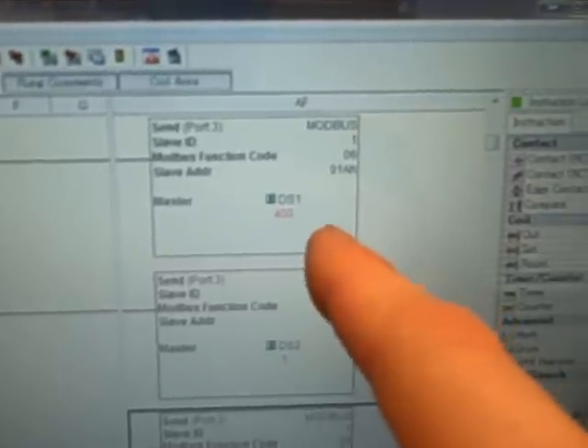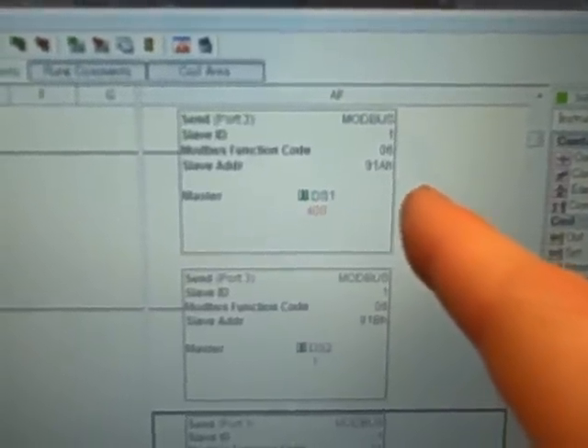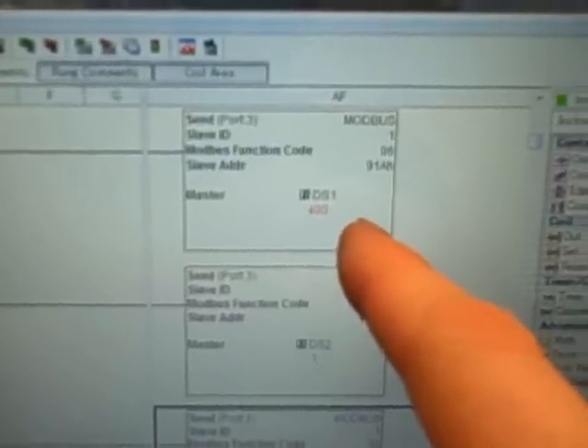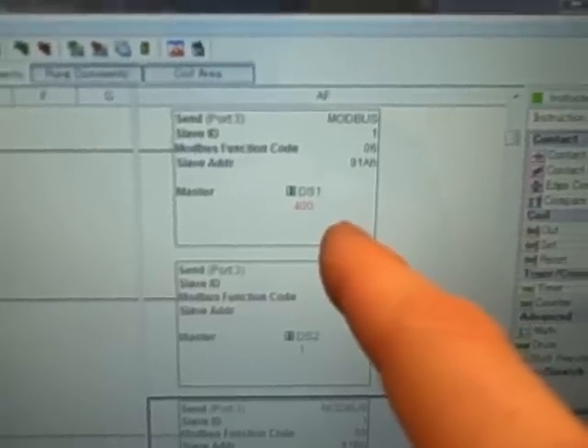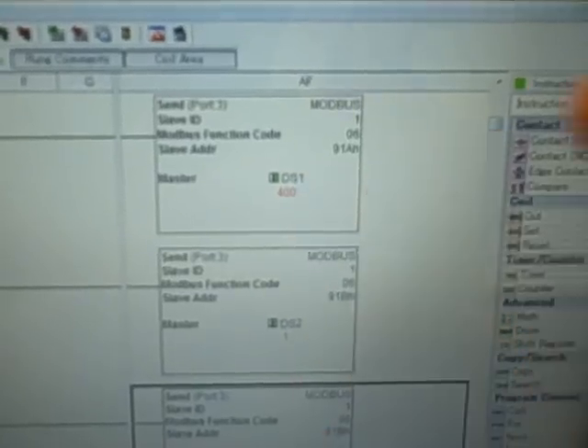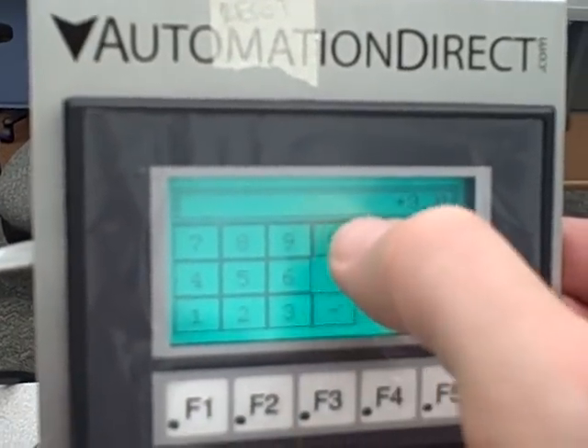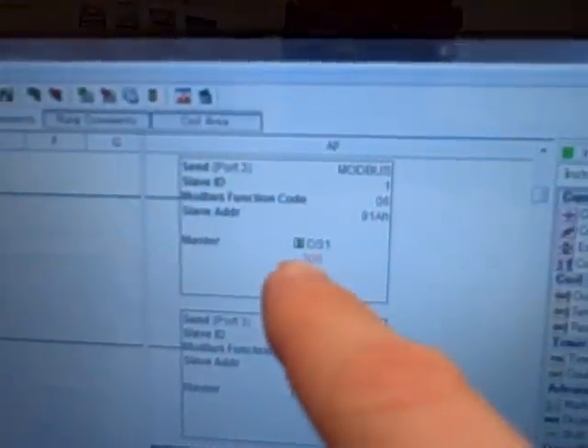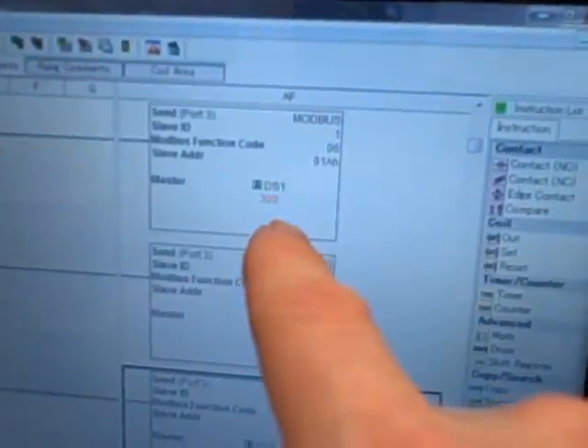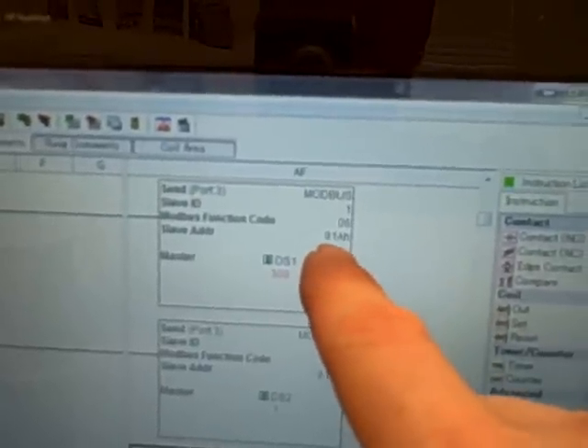Let's see what the instructions do. In this first one, we are activating this instruction on the downstroke of a half-second clock, and what this is doing is writing an integer value to the register inside the VFD that tells it the speed command. Right now the value is 400, which is a fixed-point integer number telling the frequency drive how much hertz to put out. So 400 actually means 40.0 — there's an implied decimal point. If I enter a different frequency, let's say 300, which is 30 Hz, the drive interprets that as 30 Hz even though the actual integer value in the PLC is 300. There's an implied decimal point forced by interpretation in the drive that causes 300 to be read as 30.0. This allows you to have fractional values using integer numbers. That's our speed command being written to hex address 0x91A inside the drive.